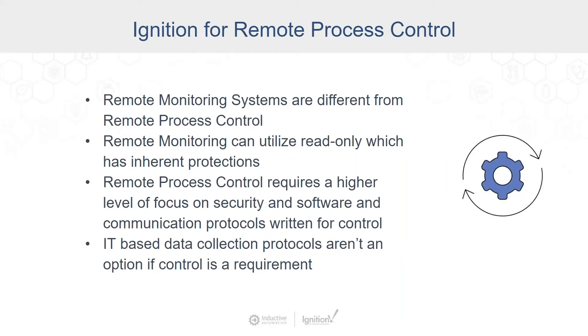If we talk about monitoring systems versus control systems for a moment, it's important to make a distinction between the two. Typically, both can be done in Ignition, and we presented a recent webinar talking about remote monitoring specifically. For monitoring, read-only connections can be utilized to provide a layer of protection. When control is being done, that's not really an option. Security becomes much more important since there's really more at stake. A lot of monitoring systems use protocols and technologies that aren't intended for robust, real-time, bi-directional communications. Using software that's written with control as a core functionality, not as an afterthought, helps a lot in the long run.